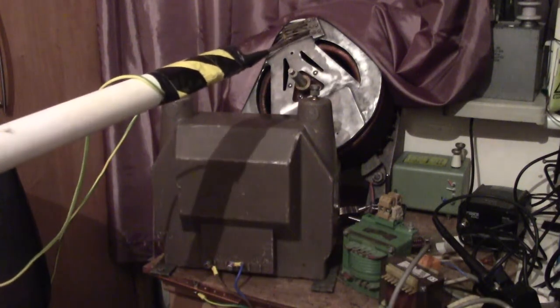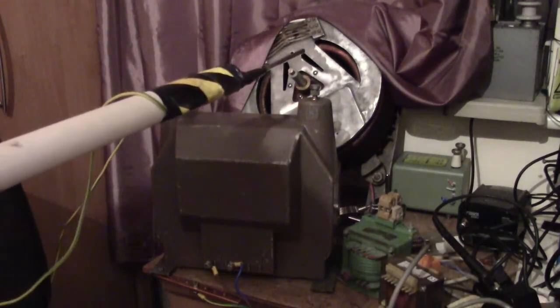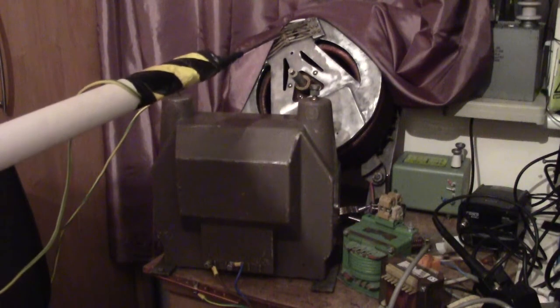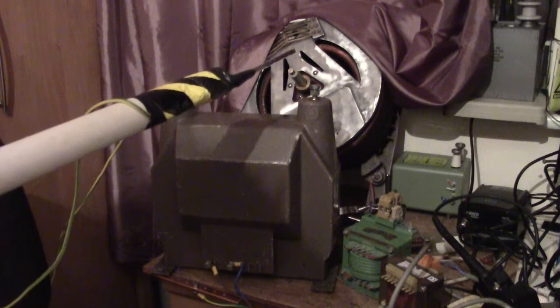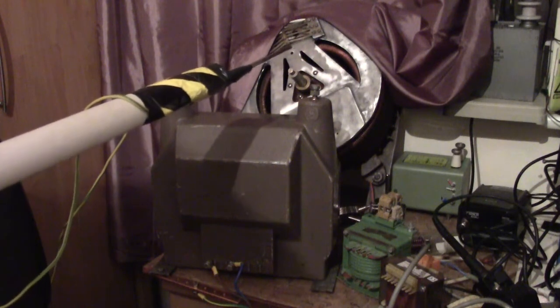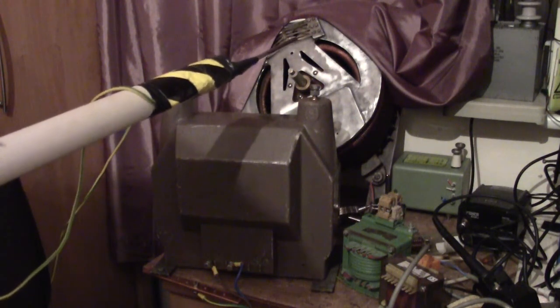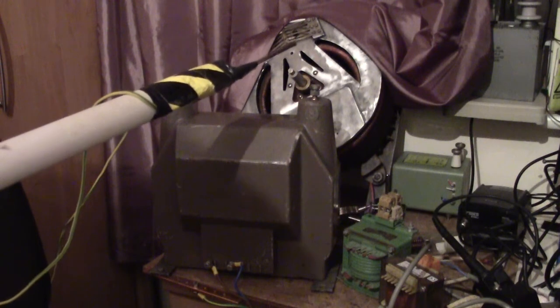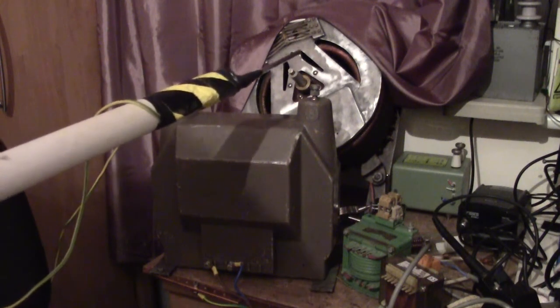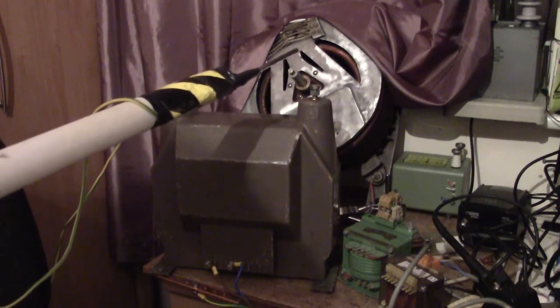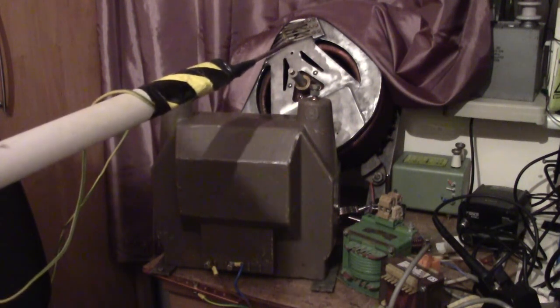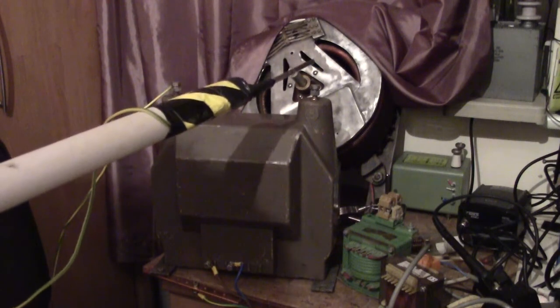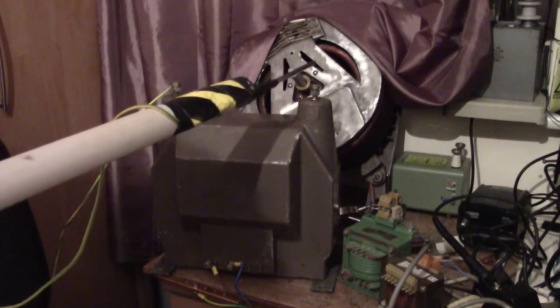So this is what happens and you'll see from how I've got a 250 watt ballast, how when the MCB trips because it's pulling too much current - it's a 10 amp MCB, it's pulling 14 amps - so it will run for a short bit and then trip out. When that trips out it will then cut down to 250 watts. So it's quite a good way to show you guys how it's all set up and working.